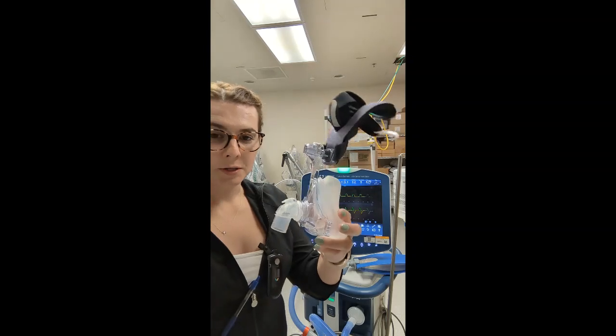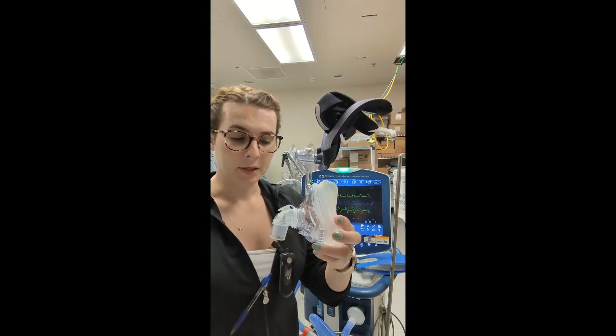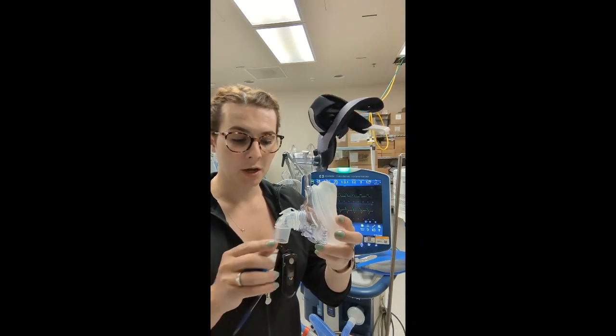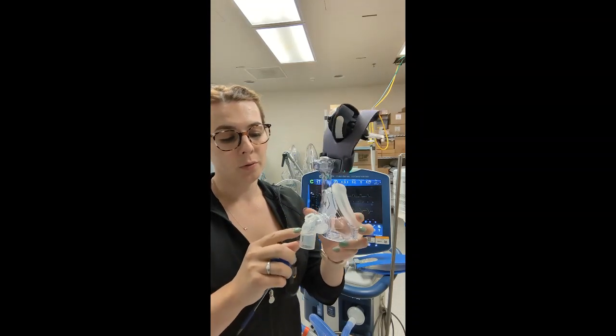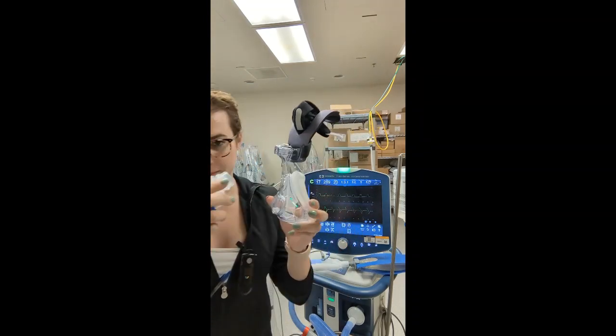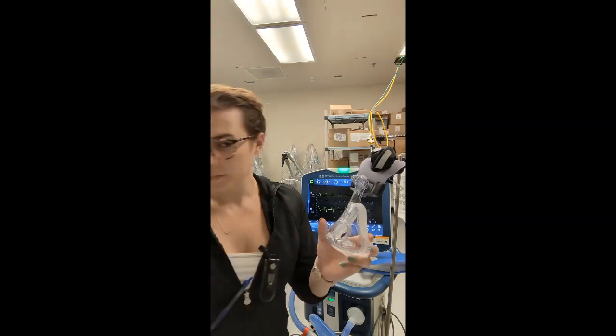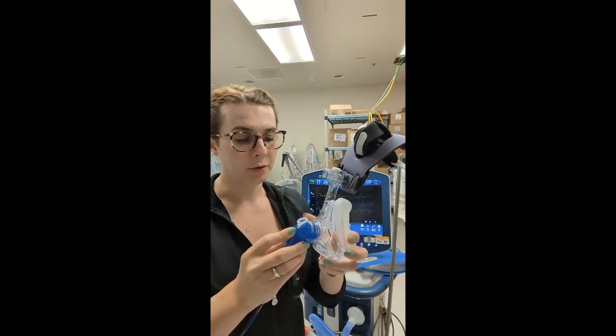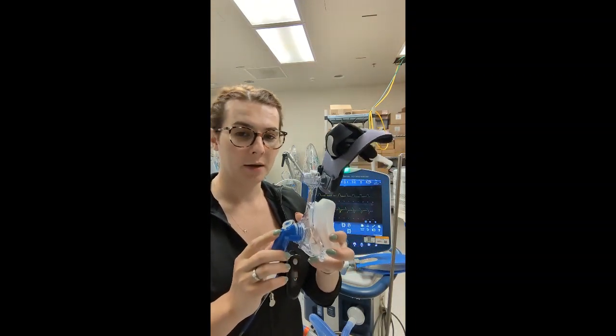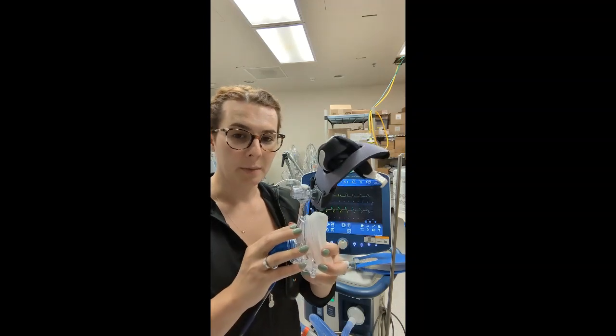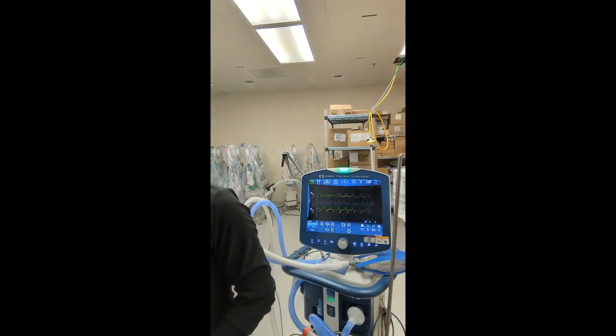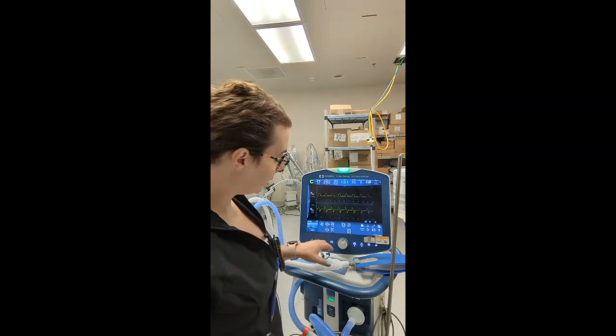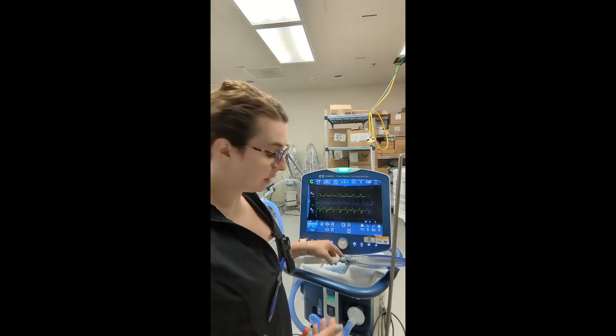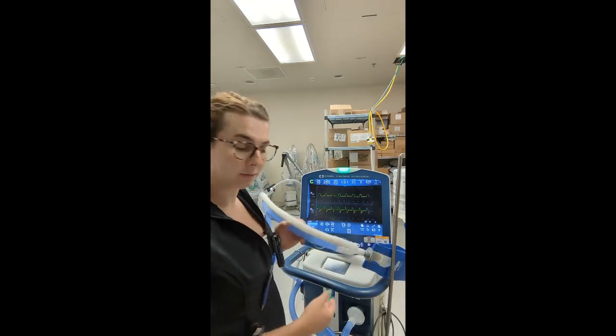So we have our patient interface that we use for non-invasive ventilation. We do need to change the elbow. We need to remove the elbow with an exhalation safety port and add the blue filter without any port. That way we could have a good proper seal on the mask and circuit. The other difference, obviously, compared to the V60 is we have a dual limb circuit.